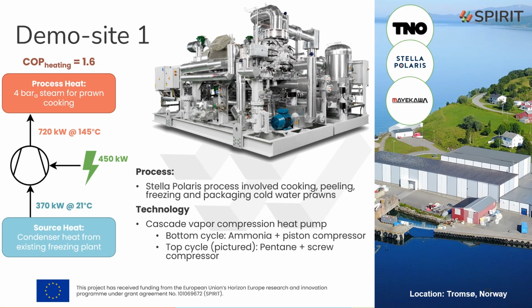One of the challenges is that the freezing plant rejects heat at around 21 degrees Celsius, meaning we need a large temperature lift of around 125 degrees Celsius. This leads to a relatively low COP, but still has good prospects from a business case, energy, and CO2 saving perspective. To achieve this large temperature lift, we'll use vapor compression heat pump technology from Mayekawa.